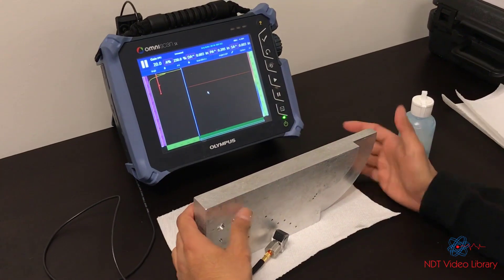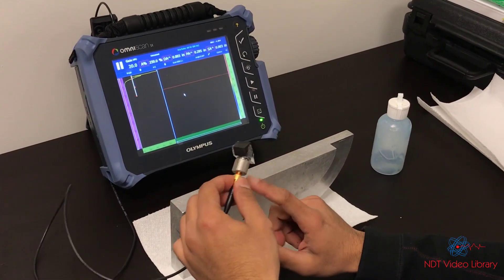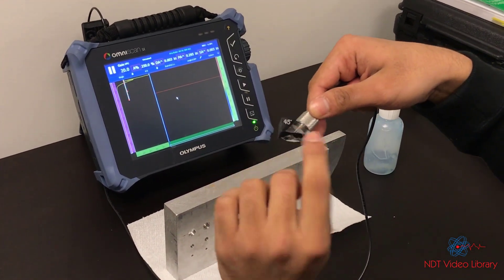We're going to learn how to do angle beam calibration for conventional UT using a 45 degree shear wave. It says 45 degree wedge and the transducer is 2.25 MHz.